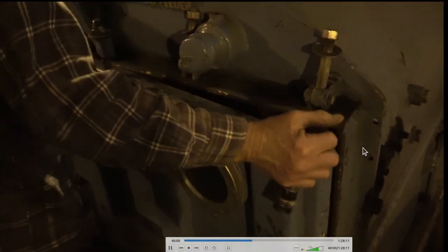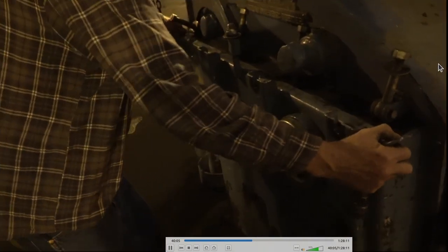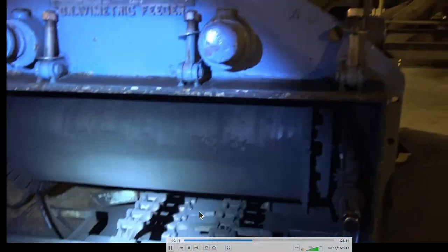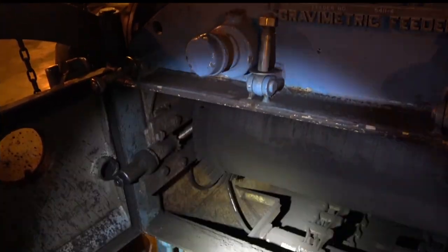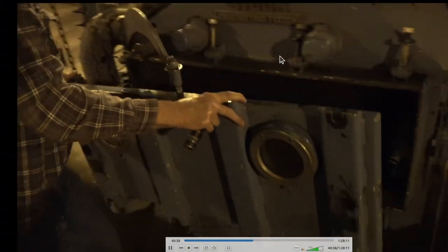There's one of the coal feeders — this one is shut down. The door is sealed tight because there's pressure on these from the pulverizer. You have a belt in here with a drag chain on the bottom. A certain amount of coal is put on the belt and there's a little bar that maintains the coal on the belt — the bar will move up and down to maintain the coal loading, then you just change the speed of the belt to determine the coal flow. They're called gravimetric feeders and they work pretty good on the feed rates of the plant.